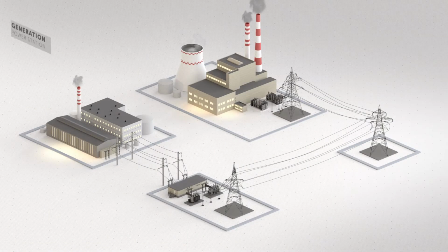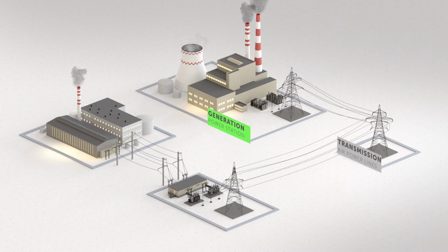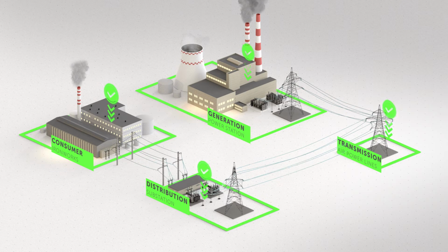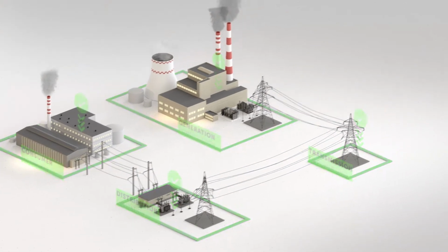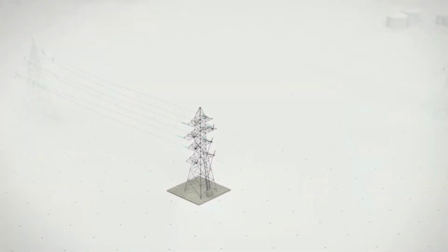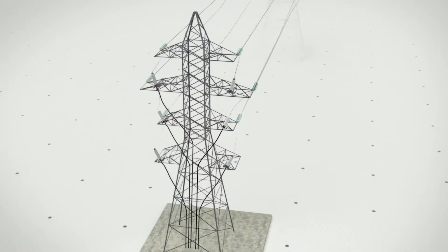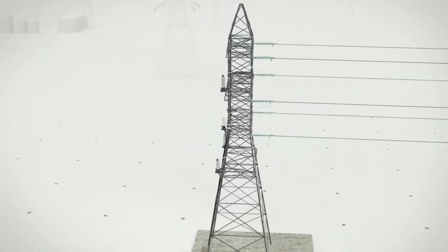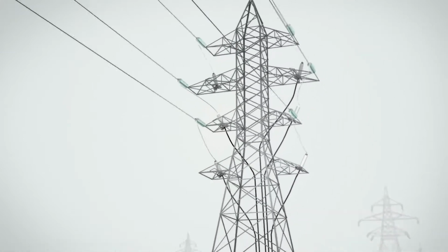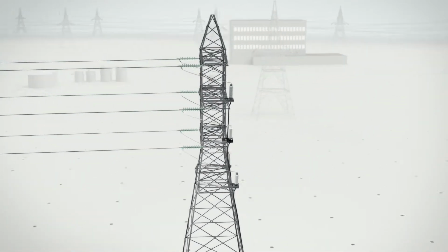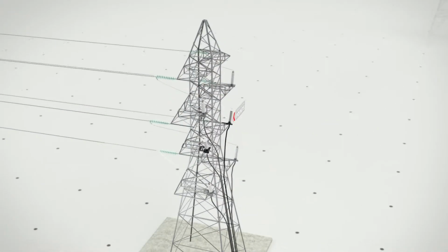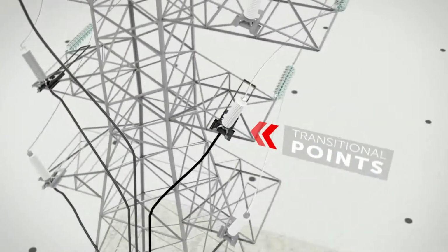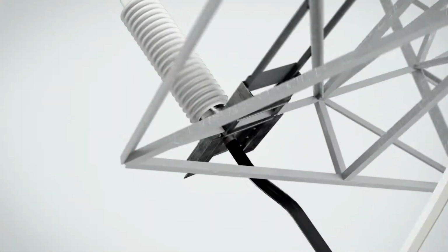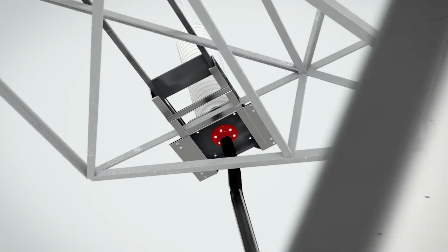Profotech's optical flexible CT can be used at all stages of the power supply circuit, from generation to consumption. Overhead power transmission lines often connect to underground cables, especially in big cities and at road, rail and river crossings. Overhead line cable joints are used at these transitional points, making them extremely difficult places from which to take current measurements. For this reason, these measurements are often not made at all.